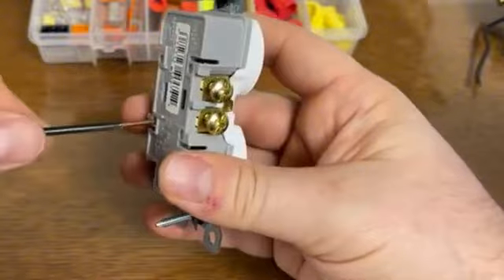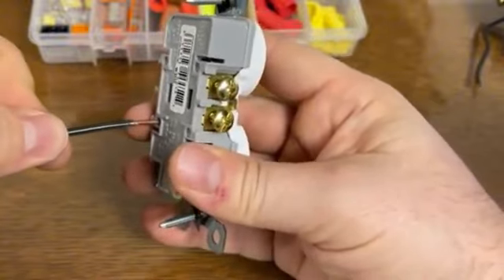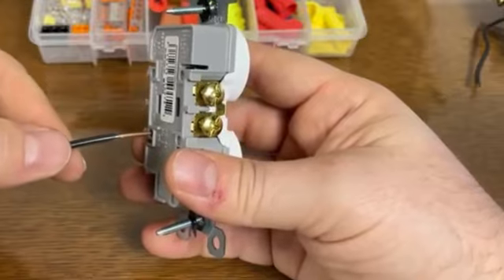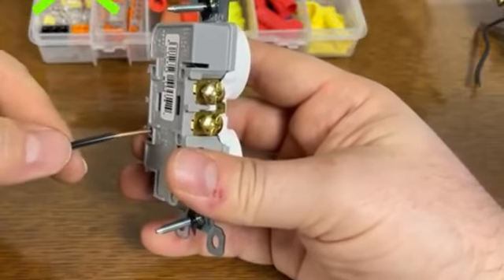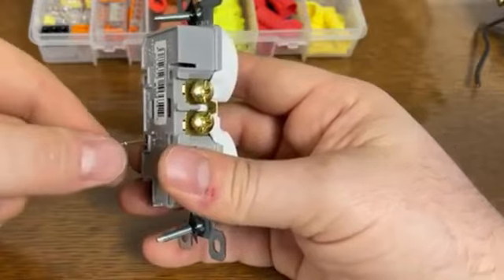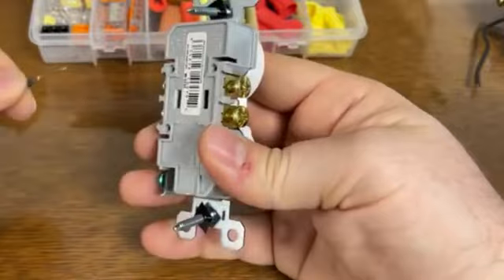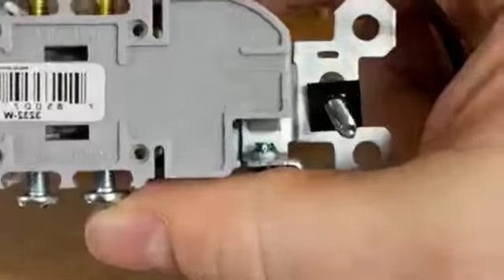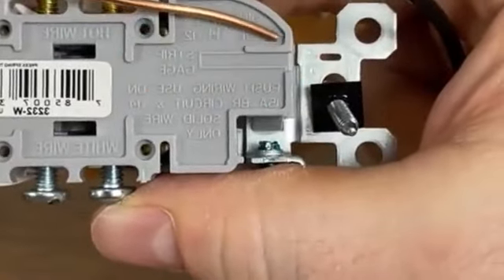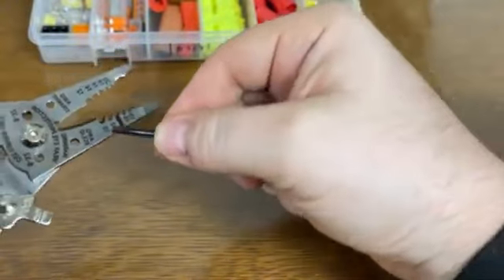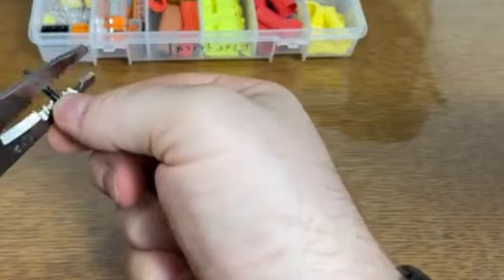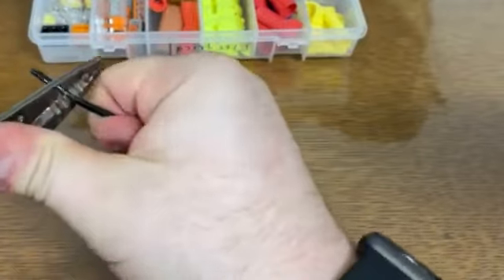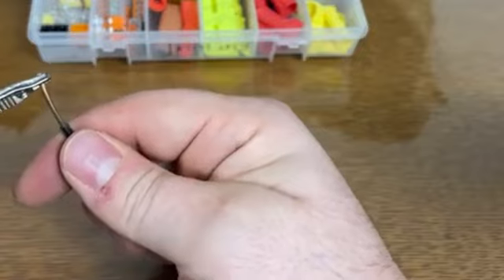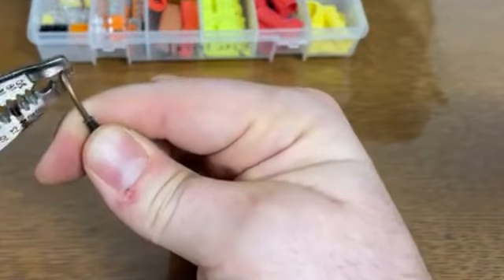The failure point is the connection. Romex connects to outlets and switches using 2 methods: screw terminals or backstab push-in terminals. Screw terminals require stripping wire, wrapping it clockwise around a brass screw, and tightening to proper torque. It takes 30 seconds per connection. Backstab terminals let you strip the wire and shove it into a spring-loaded hole on the back of the device. It takes 3 seconds. On a house with 200 connections, that is 90 minutes of labor costs. Builders use backstabs on every outlet and switch they can.